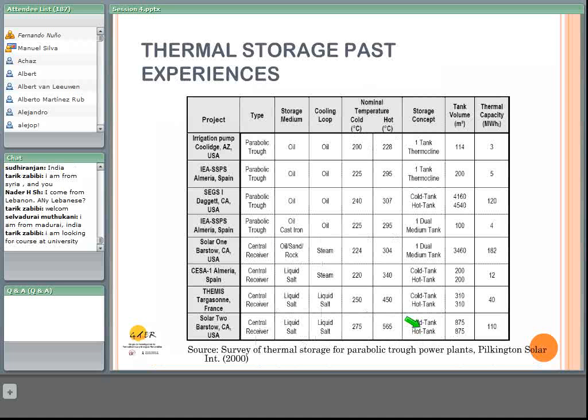I just want to call your attention to the fact that the most significant experience with molten salts, or liquid salts, was at the Solar 2 project in Barstow, California, in the United States. The thermal capacity of this system was 110 megawatt-hours thermal, with a temperature in the cold tank of 275 degrees C and a temperature in the hot tank of 565 degrees C - almost 300 degrees difference between the hot and the cold tank.